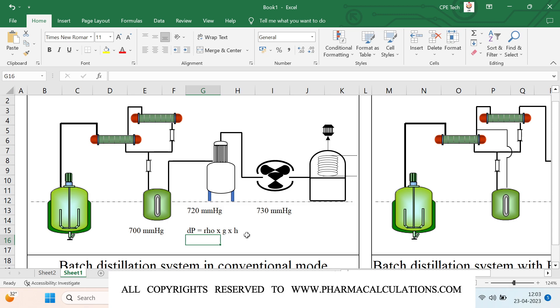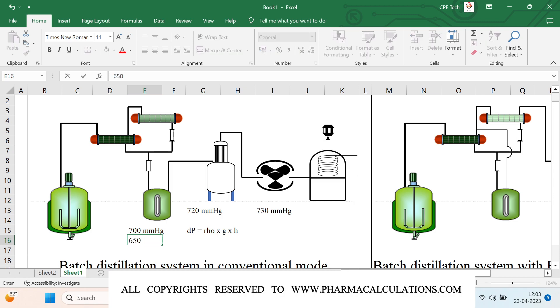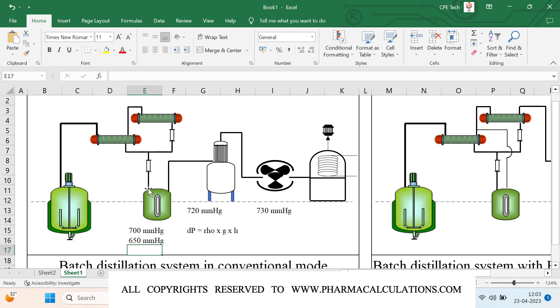Using this formula, you can calculate ΔP depending upon the height H. Here, g is the acceleration due to gravity, approximately 9.81 m/s², and ρ is the density of the liquid flowing down. Initially you may have 700 mmHg, but as the collection increases, the height effect causes the vacuum to drop to around 650 mmHg. This depends on the height of the collection line, and this reduced vacuum in the collection receiver automatically has some impact on the vacuum generation inside the reactor.